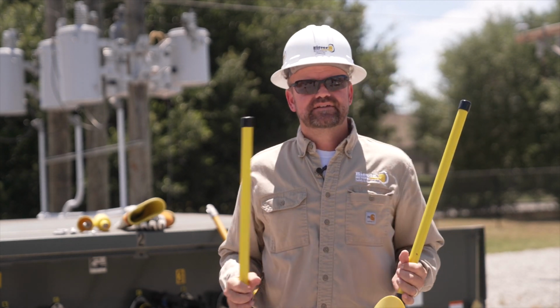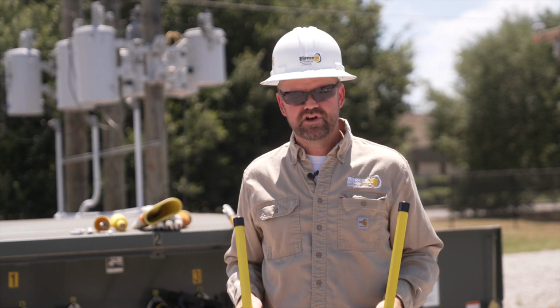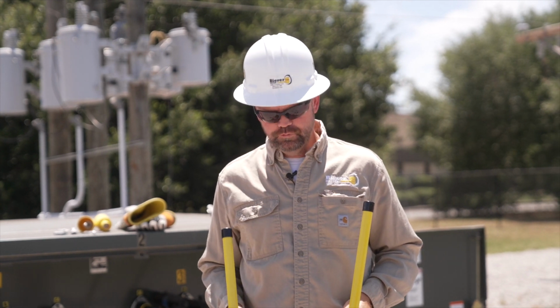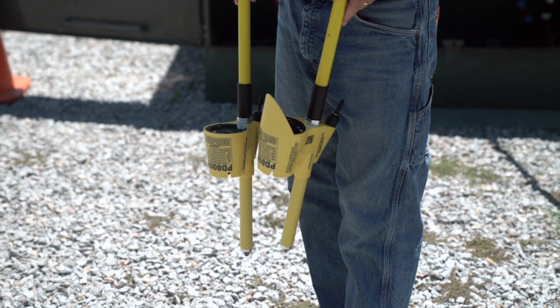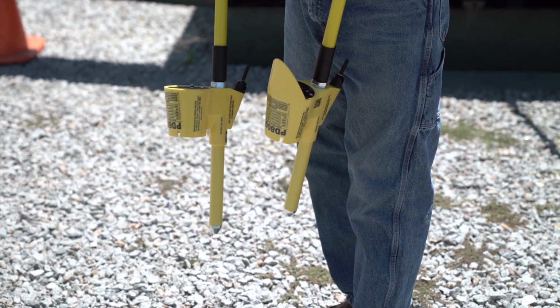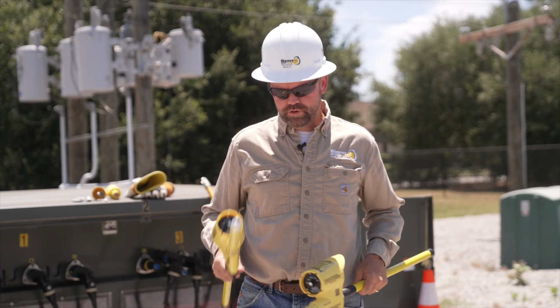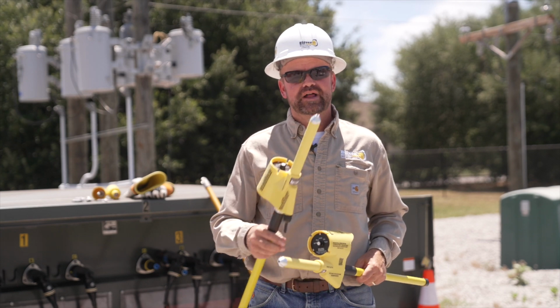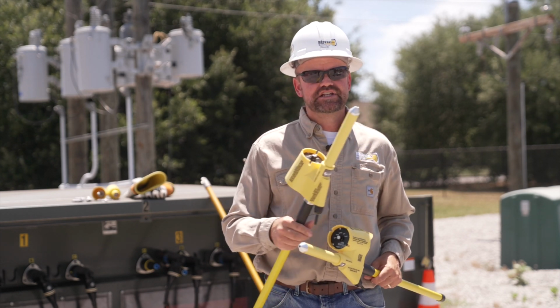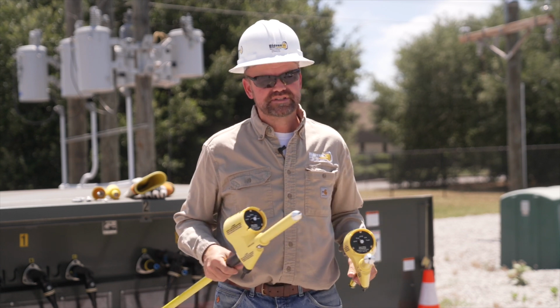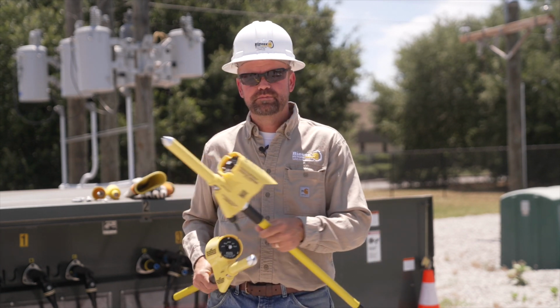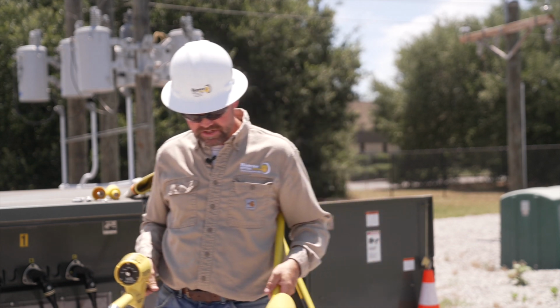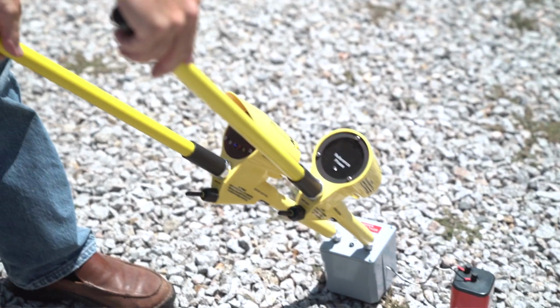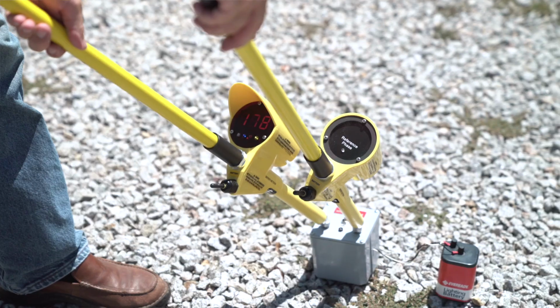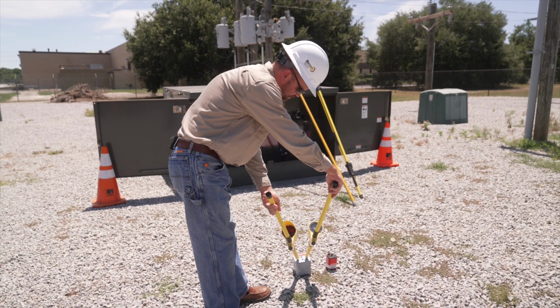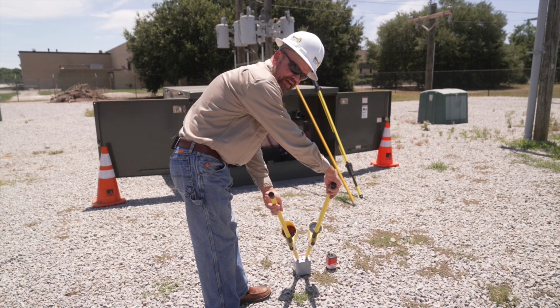Once I've done that, again, I recommend that you test the device on a known potential, and the dual phase power supply that is an option with the kit should register 180 degrees out of phase. So in order to test the device on the dual phase power supply, turn both probes to the DEG switch position, so the meter probe is in the DEG and the reference probe is in the DEG. Now I can actually test to see my out of phase reading, and it should be near 180 degrees since this is a dual phase power supply.